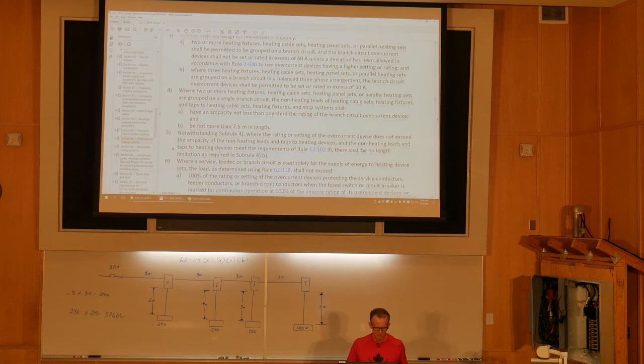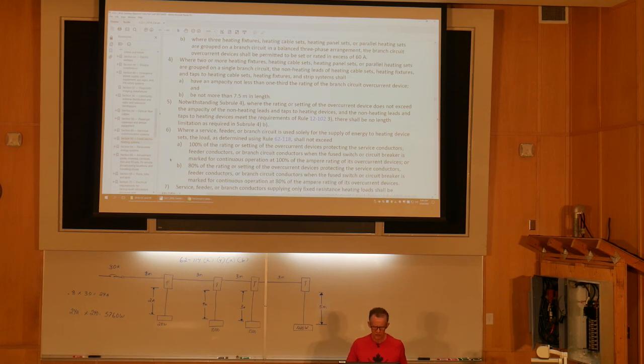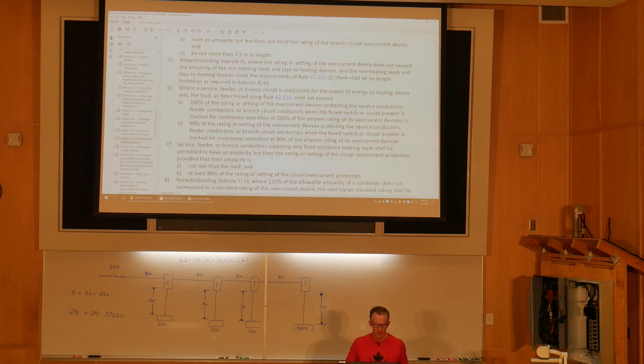Just a statement there. 6. Now we're getting into the good stuff. Where a service, feeder, or branch circuit is used solely for the supply of energy to heating device sets, the load as determined using 62-118, that's the demand factor rule, we'll look at that later, shall not exceed 100% of the rating or setting of the overcurrent devices protecting the service conductors, feeders, or branch circuit conductors when the fuse switch or circuit breaker is marked for continuous operation at 100% of the ampere rating of its overcurrent device.